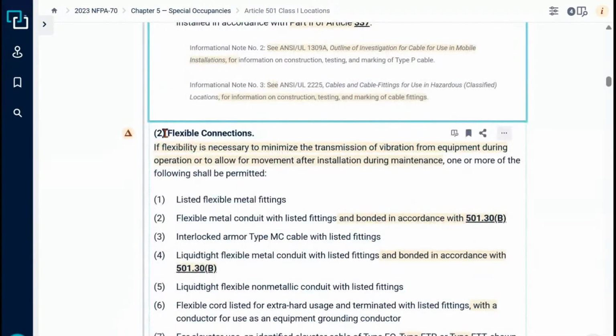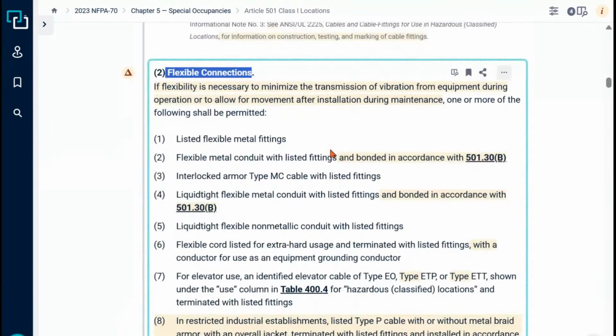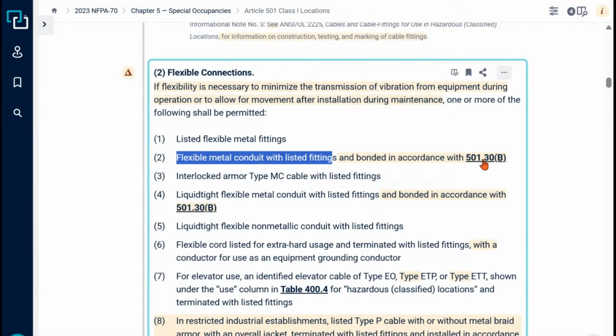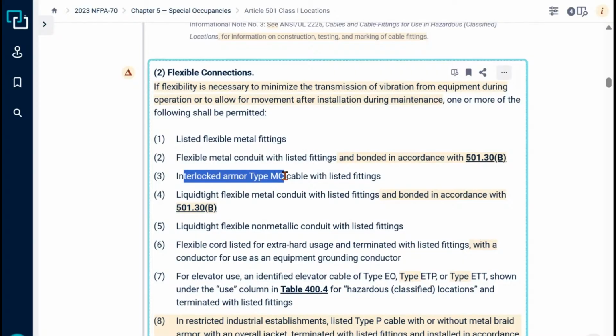And then when you see flexible, okay, we're in this location, right? So this is a Division 2 location of a Class 1. Look how it opens up. You can use flexible metal fittings. You've got flexible metal conduit with a listed fitting and bonded in accordance with what we saw in 501.30(B), which is going to send you to 250.102. Most notably, probably (E), because it's going to talk about raceways and things like that and bonding. And you've got interlocked armor MC. That's the standard MC with a standard MC fitting.